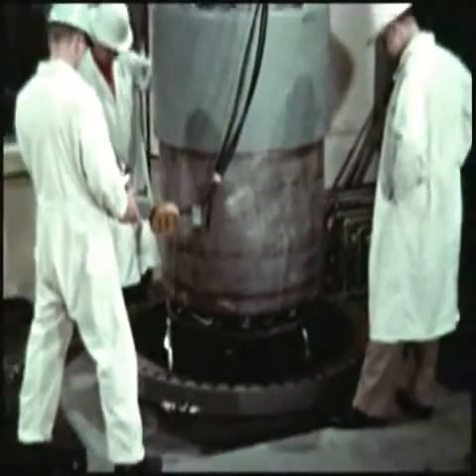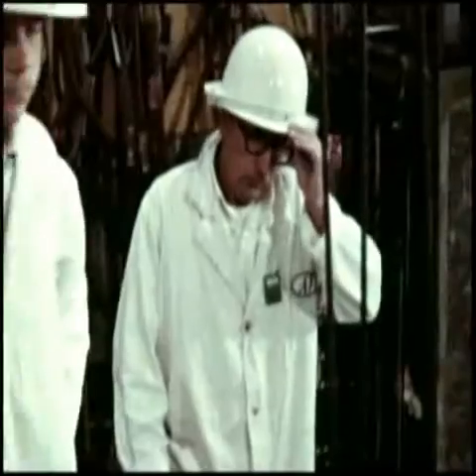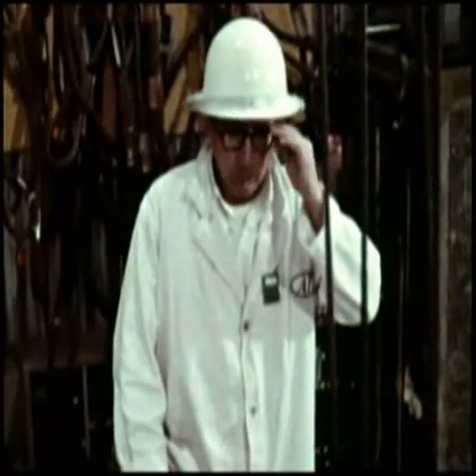The reactor heat is transferred from a shielded and contained NaK primary loop through an intermediate heat exchanger to a secondary non-radioactive NaK system, which in turn dissipates the reactor heat to the atmosphere. A removable clean room is placed over the containment vessel prior to reactor core installation.